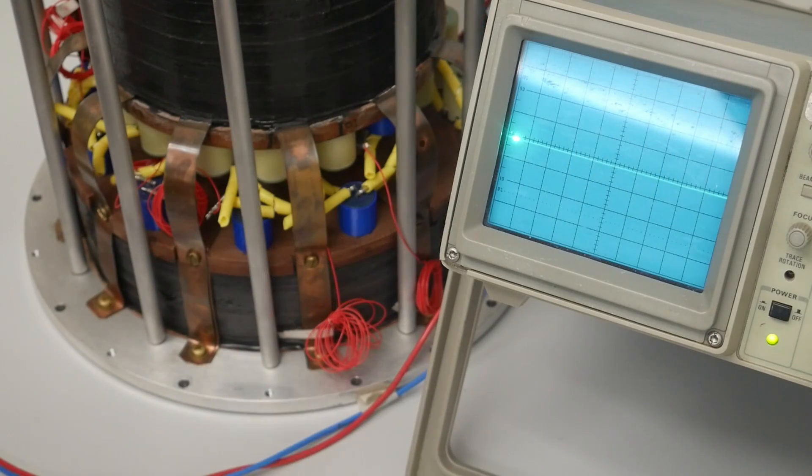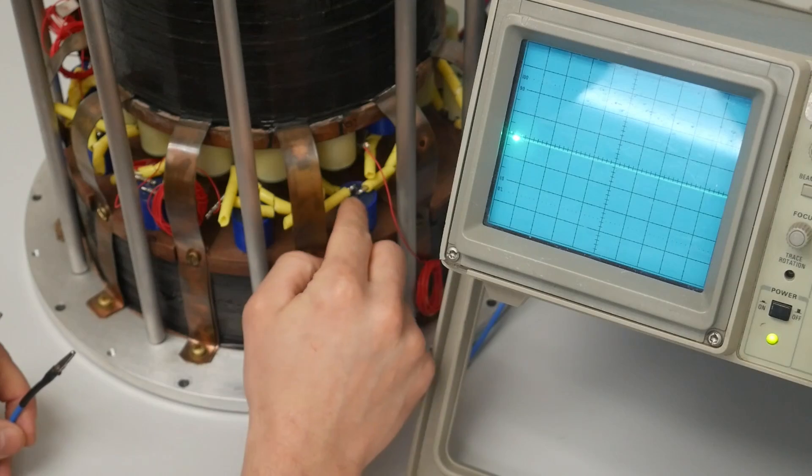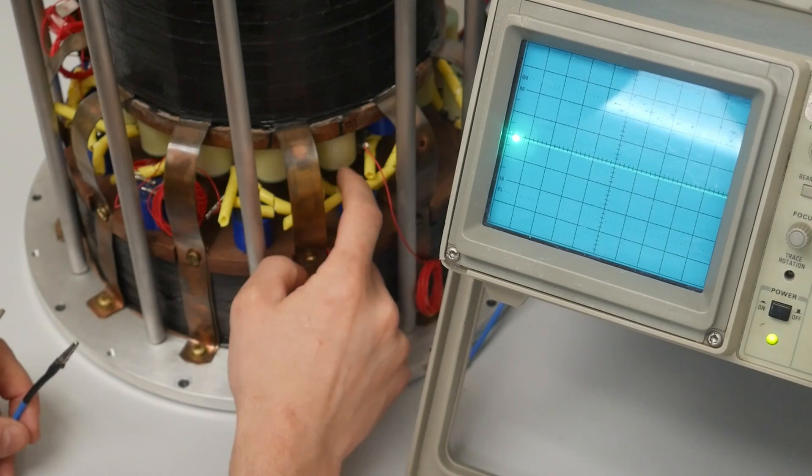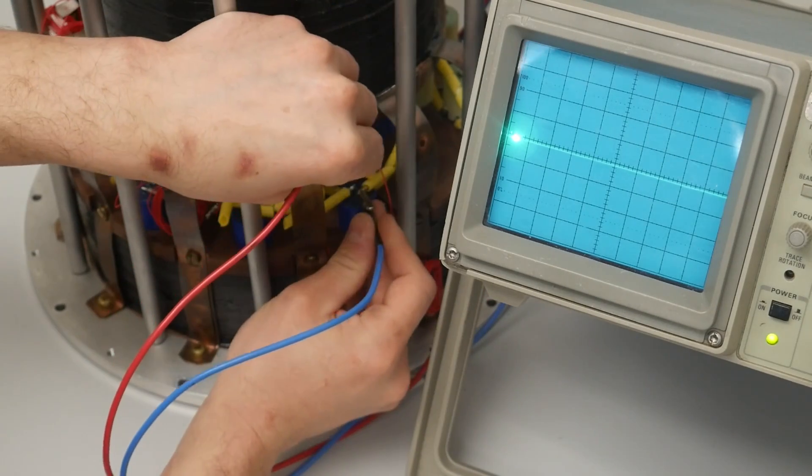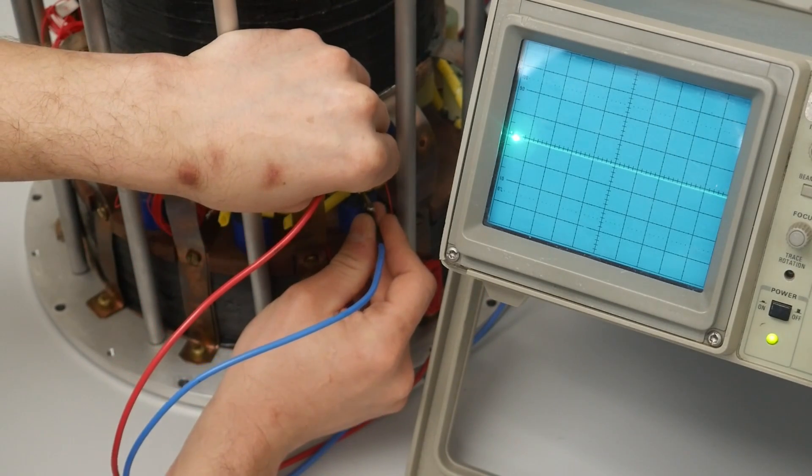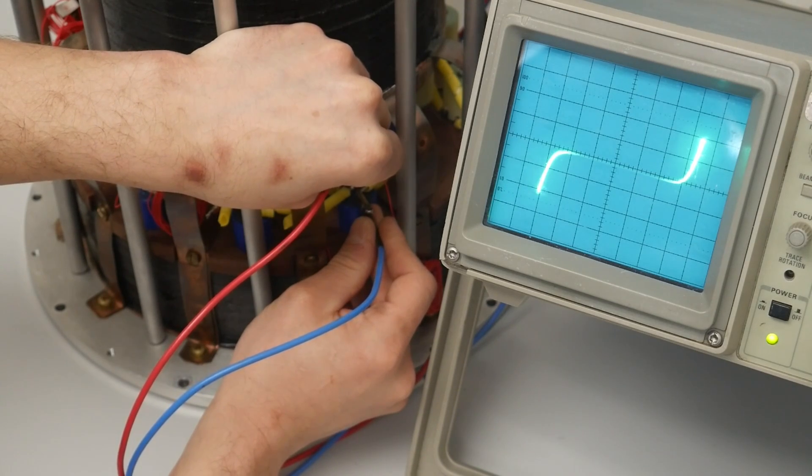Here's a magnet that is still older but it has the modern diode package. To look at these diode packages, you have two wires coming into each one. Simply take your curve tracer leads, whatever they may be, and go across each diode, and you'll be able to test each diode one by one as you go around the magnet.